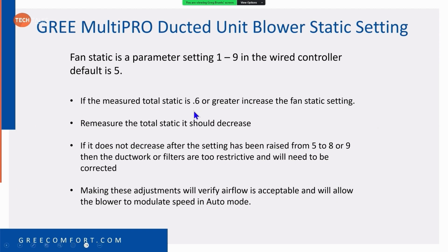Then let's say we get 0.6 or higher. Remeasure the total static pressure, it should decrease, because essentially what you're doing is setting the blower to a higher torque to overcome higher static. My caution to you is, let's say I measure on a unit and I get like a 0.8. So I take that from the default of 5 and I cram that thing all the way up to, let's say, 9. Then I remeasure my total static and it hasn't come down any.